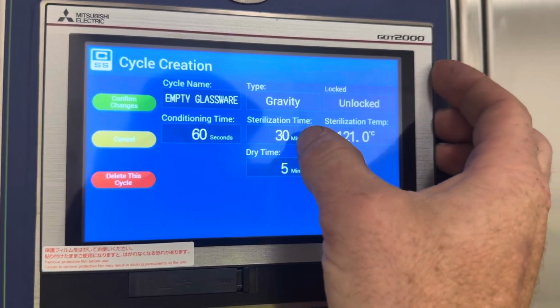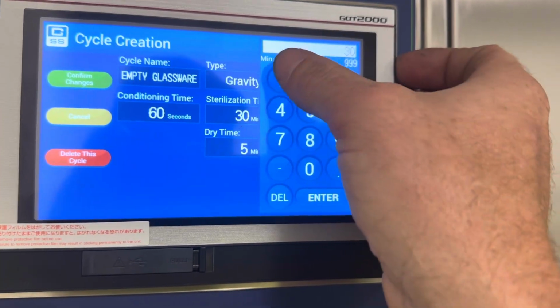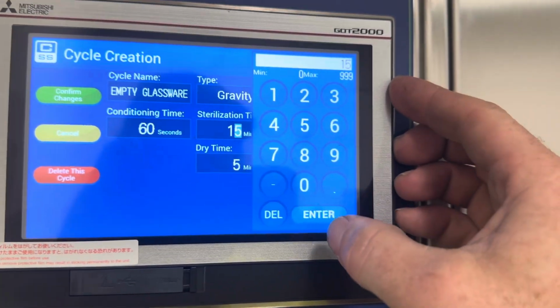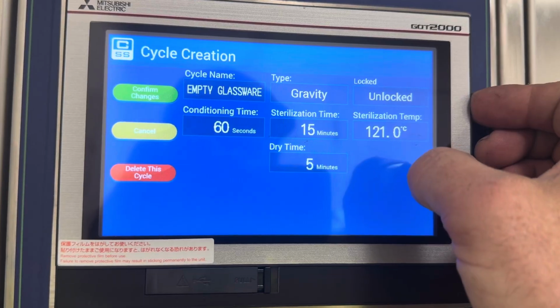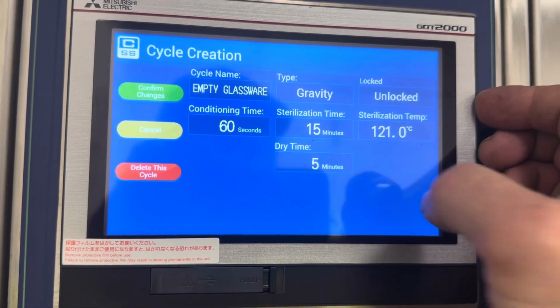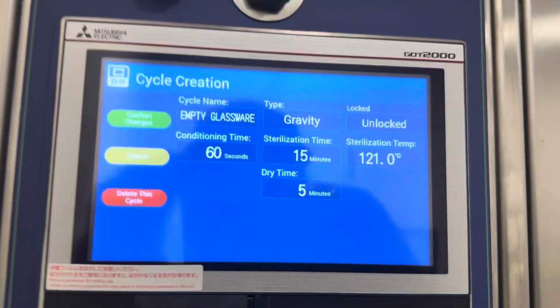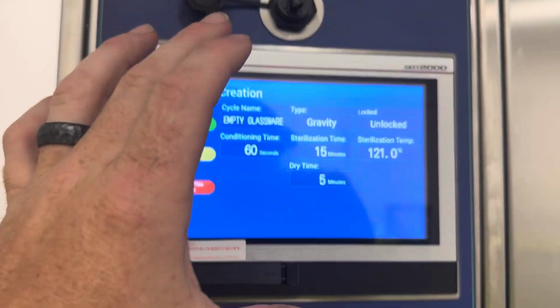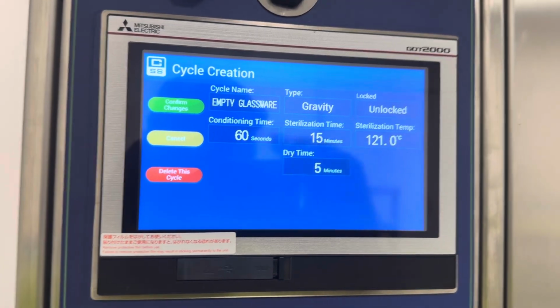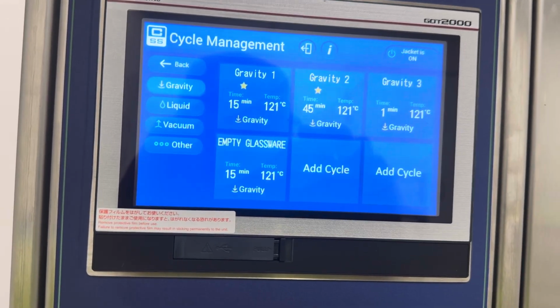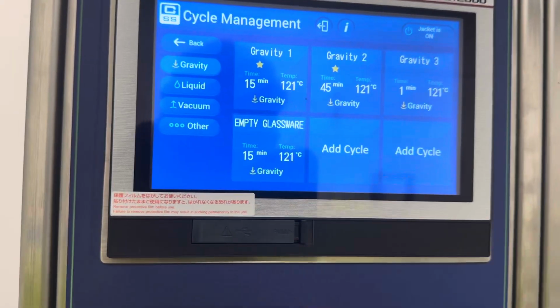Conditioning time, 60 seconds, that's perfect. Sterilization time, I'm gonna go 15 minutes. Sterilization temp, 121. Dry time, 5 minutes, that looks perfect. Once I've confirmed my parameters for the cycle, I'm gonna put confirm changes. Okay, now we have this new cycle right here.